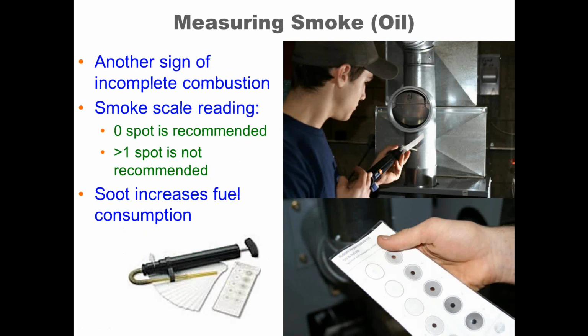We talked about the formation of carbon particles or soot as a sign of incomplete combustion, that you're on the wrong side of the curve or on the wrong side of operation. Usually 0 smoke spot is recommended. Greater than 1 smoke spot is usually not recommended because, in addition to showing that you're incompletely burning and not getting the value out of your fuel, it can also increase fuel consumption by actually forming an insulative layer inside the refractory of the burner compartment.